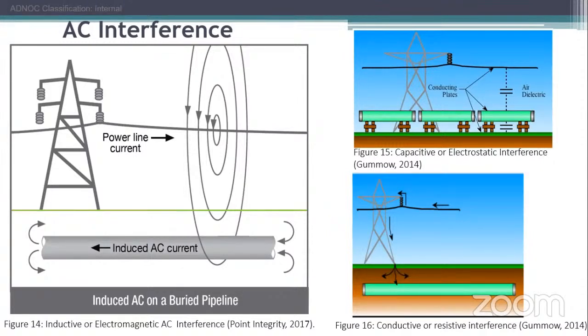For capacitive to happen, that means I'm constructing a pipeline close to a high voltage transmission line, and I can prevent it easily by being careful. For conductive, we can also guard against it, since it happens only when the lightning is massive. But inductive happens during normal transmission, when you're just transmitting power and your pipeline is running, this problem is there.